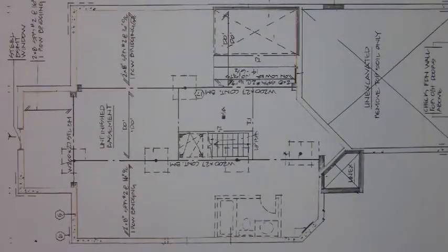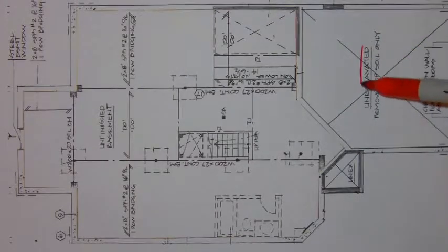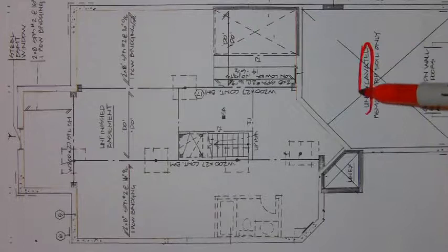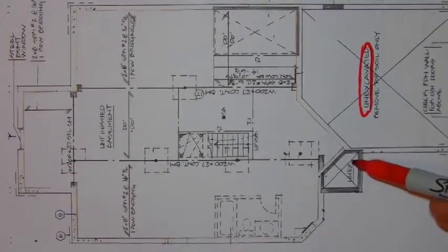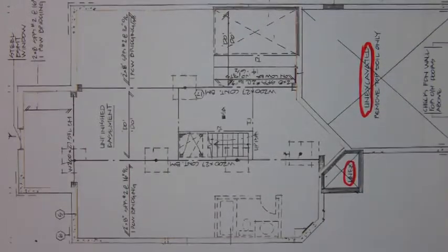Just as a reminder, whenever you see anything that says unexcavated, this area or these areas are not included in your heat loss calculation, and therefore you must ignore these foundation walls as they are not part of the basement where there will be experiencing heat loss.